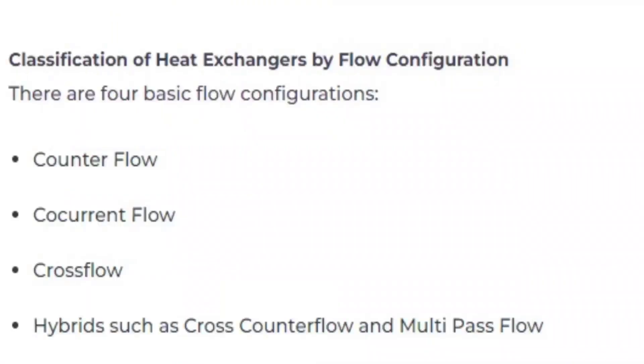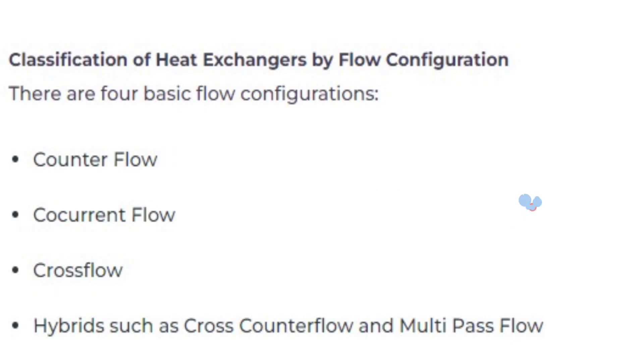There are four basic flow configurations of heat exchangers. In an idealized counterflow exchanger, the two fluids flow parallel to each other but in opposite directions. This type of flow arrangement allows the largest change in temperature of both fluids and is therefore the most efficient, where efficiency is the amount of actual heat transferred compared with the theoretical maximum. In co-current flow heat exchangers, the streams flow parallel to each other and in the same direction; this is less efficient than counterflow.